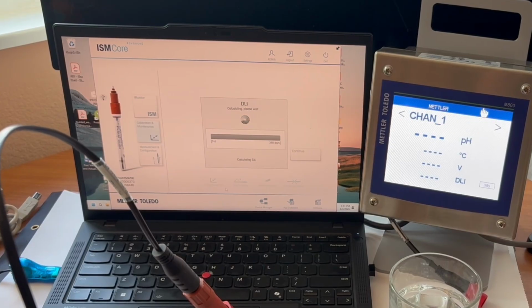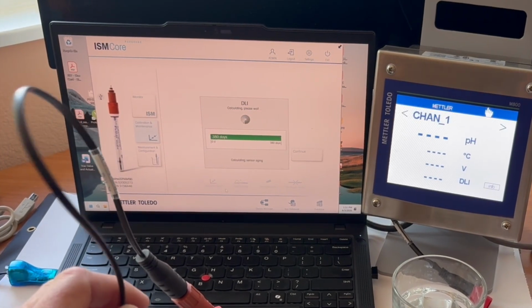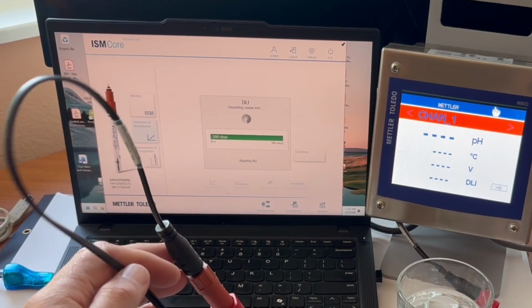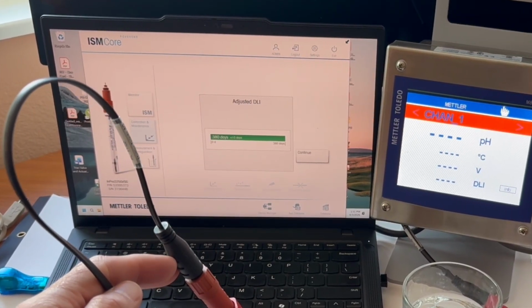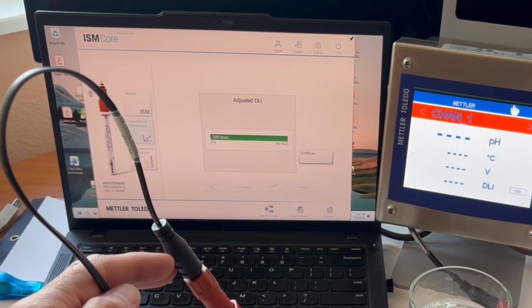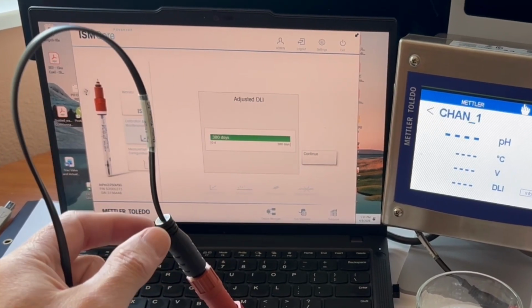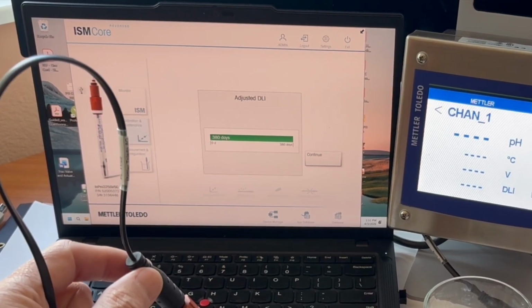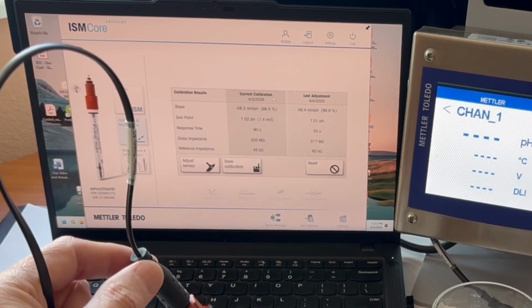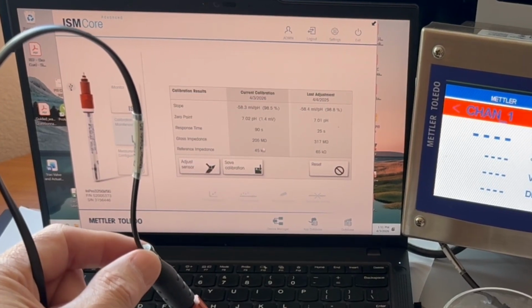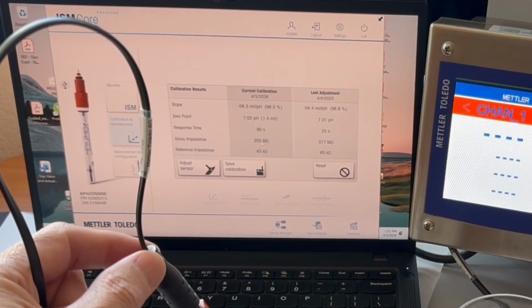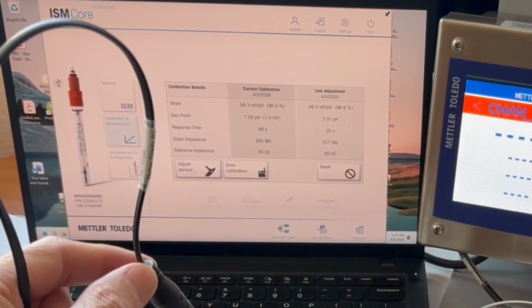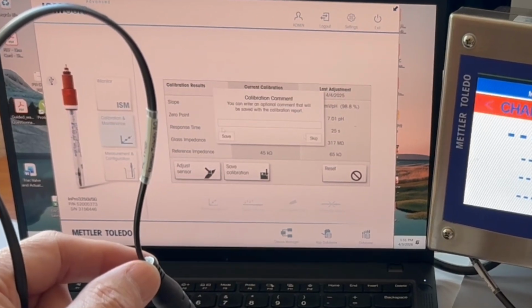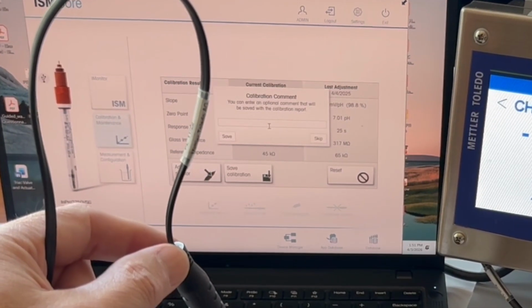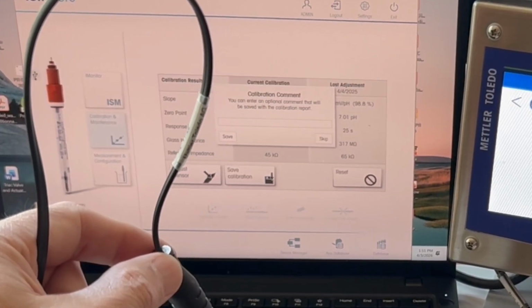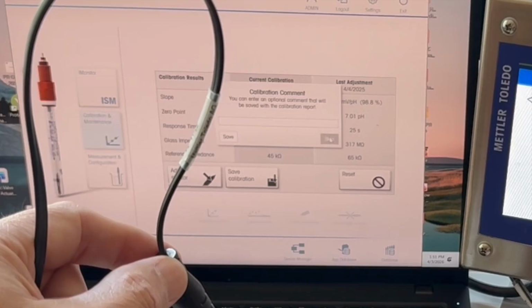What it does at this point is, because the dynamic lifetime indicator is dynamic, it will add or sometimes subtract days of life. But in this case, it says the adjusted DLI is still sitting at 380 days. Again, this probe has not seen any process. It's just been sitting in and out of buffers. So there we say continue, and it then shows what the data is for this sensor. So the current calibration here in the center gives us the slope, the offset, etc. I'm going to say adjust sensor. This is if I wanted to add a comment like, hey, this sensor is going to be installed in the alky unit at the refinery, whatever.